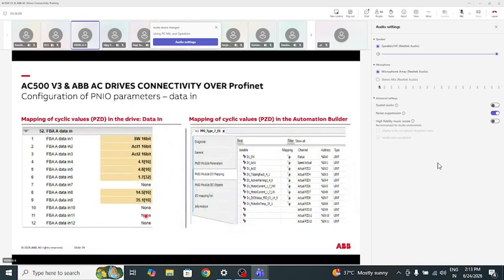Next, for Modbus, register mapping was important, whereas in Profinet, you require a GSDML file. Each slave device will have its own GSDML file. It will have the data about the inputs and outputs for exchange. So you need to download the GSDML file from the product website. That needs to be loaded into the automation builder. Using that you can do the mapping.